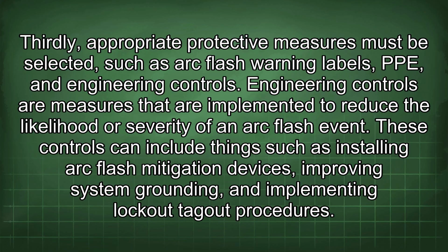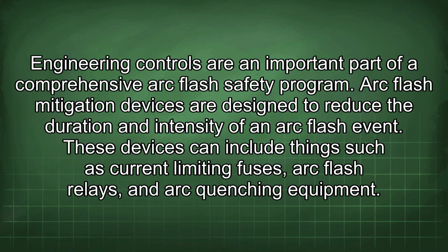Engineering controls are measures that are implemented to reduce the likelihood or severity of an arc flash event. These controls can include things such as installing arc flash mitigation devices, improving system grounding, and implementing lockout-tagout procedures. Engineering controls are an important part of a comprehensive arc flash safety program.